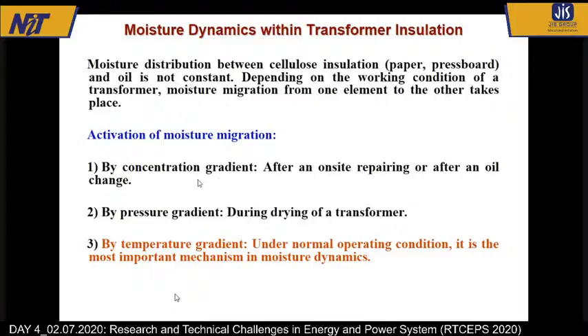Concentration gradient happens when we replace the oil, then suddenly the new oil becomes dry while the paper is already there inside and it already has moisture. So concentration of moisture in paper is higher than in the oil. So what happens? Moisture moves from higher concentration to lower concentration. Then pressure gradient. Sometimes we do the drying of a transformer with a vacuum pressure chamber. Because of that, the moisture comes out of the paper. This is migration. But these are all special cases. Either oil is replaced or the transformer is dried.